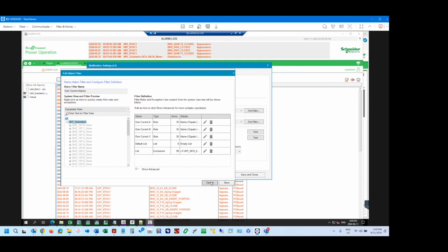Yeah, that's basically a connection to itself. An example is right now our configuration is we're running two feeders that are connected. It actually wasn't that way now, but it was for a period of time that we were using two of the feeders, backfeeding them from T2. The condition was that the two feeders running in parallel, both of these added together, had to be below 800 amps. So I needed to add one feeder plus the other feeder to equal 800 or less. That could only be done at a VIP level. I can't do that at a meter level, because you're tying two of them together. Yeah, it makes sense to do it at the VIP level.